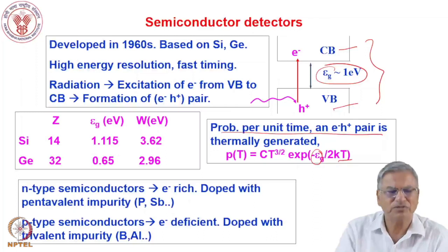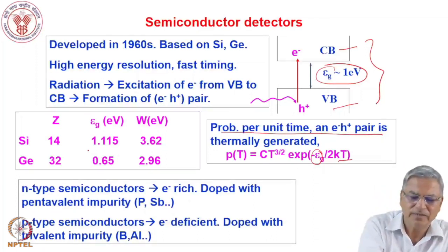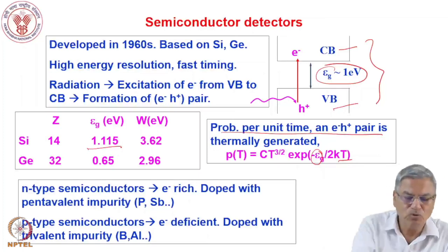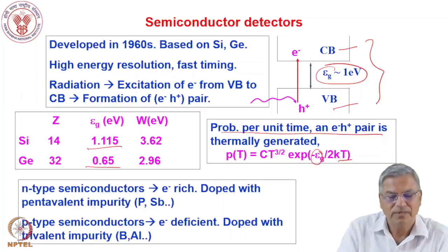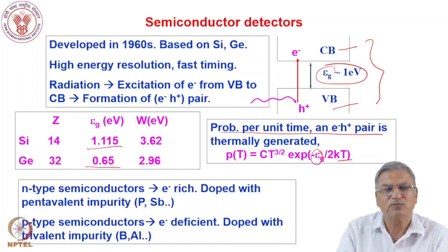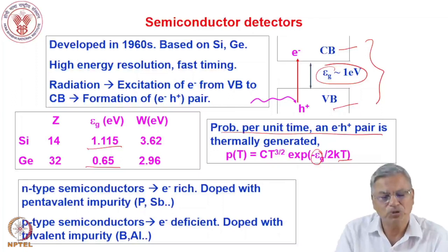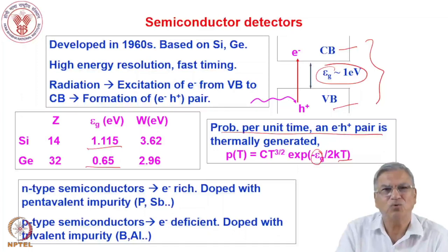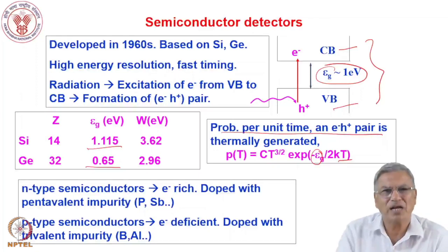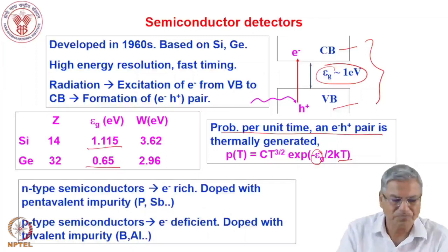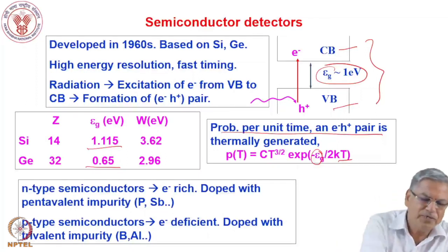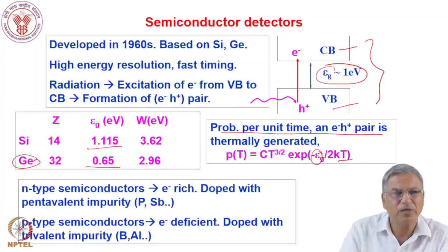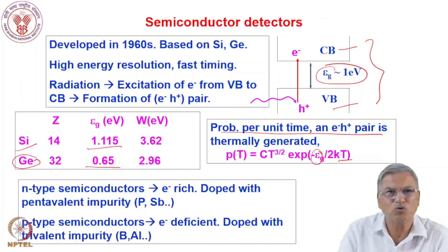The band gaps of the main detector materials are: silicon at 1.115 eV and germanium at 0.65 eV. The W values — energy required to create one electron-hole pair — are higher than the band gaps, as in gaseous media, because not every interaction leads to electron-hole pair formation; sometimes electrons and holes get trapped and are not collected. Germanium, being higher Z, is used mainly for gamma ray spectroscopy, while silicon, being lower Z, is used for alpha counting and other charged particles like protons and heavy ions.